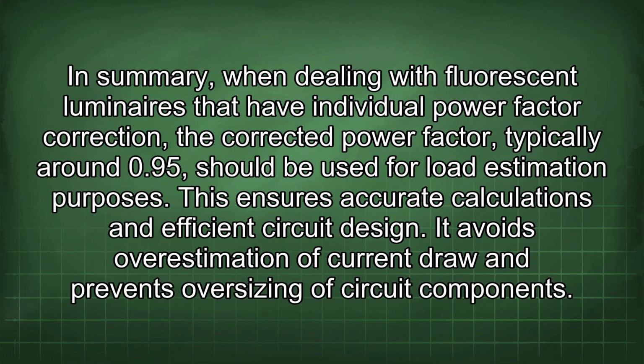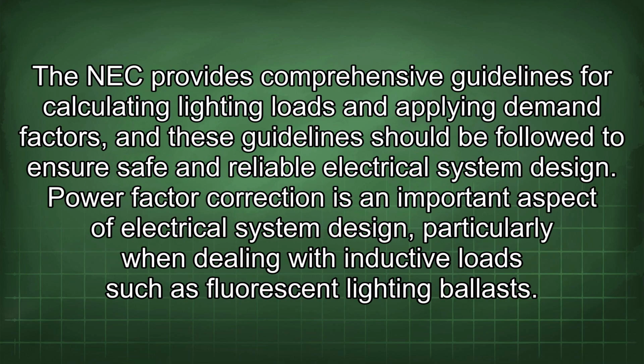In summary, when dealing with fluorescent luminaires that have individual power factor correction, the corrected power factor, typically around 0.95, should be used for load estimation purposes. This ensures accurate calculations and efficient circuit design. It avoids overestimation of current draw and prevents oversizing of circuit components. The NEC provides comprehensive guidelines for calculating lighting loads and applying demand factors, and these guidelines should be followed to ensure safe and reliable electrical system design.